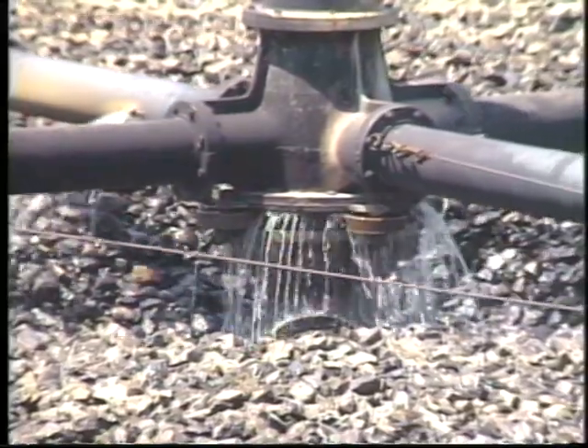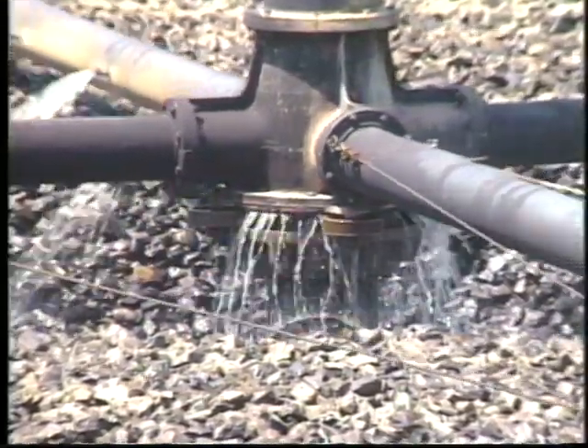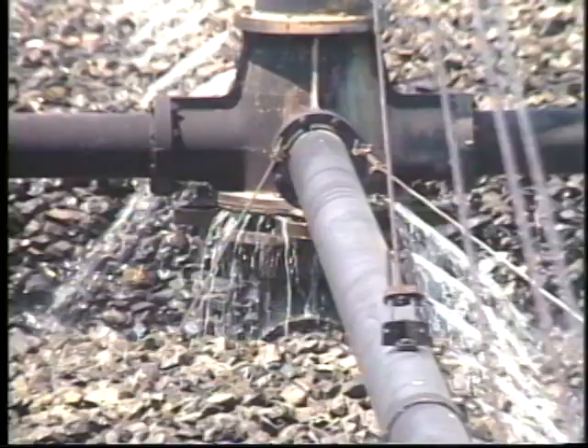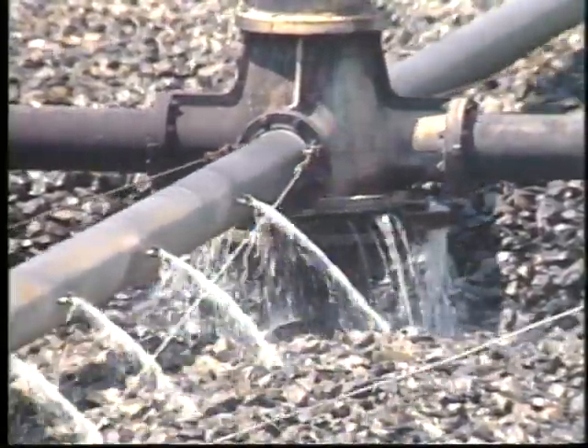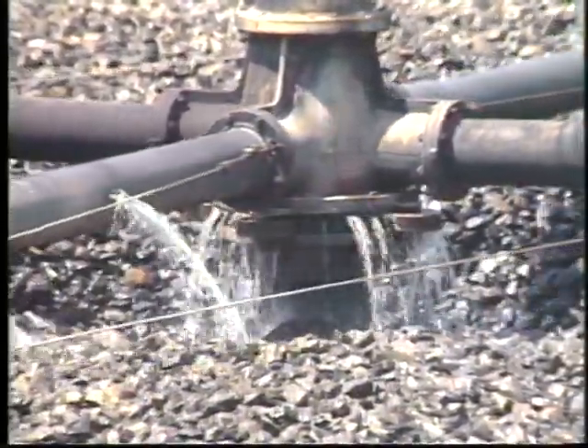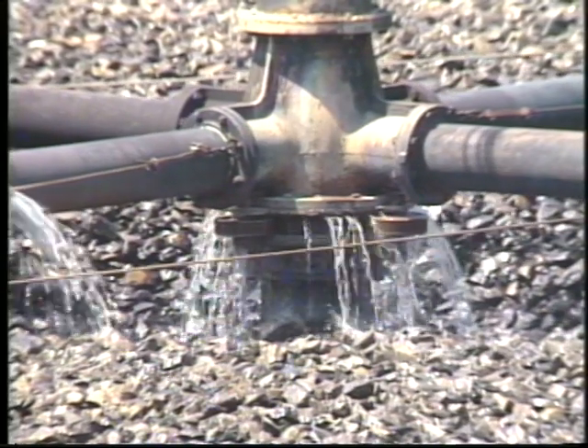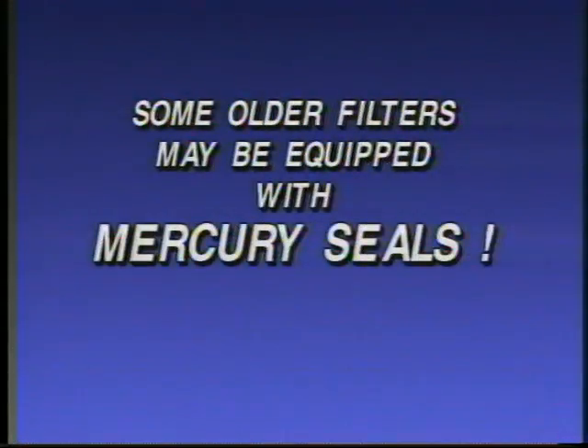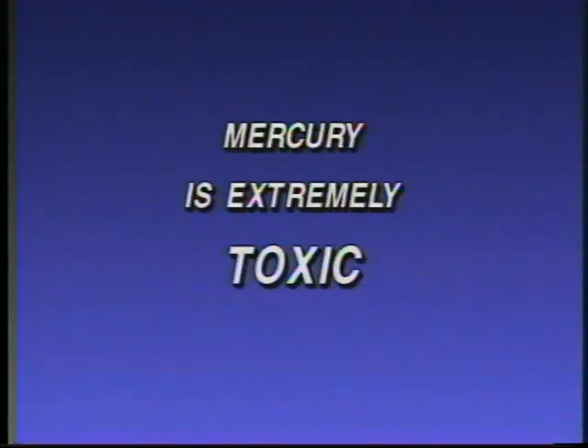If the seal in the center column is leaking excessively, it should be replaced. Leaking seals can lead to poor trickling filter performance. Warning: some older trickling filters may be equipped with mercury seals. Mercury is an extremely toxic element that requires special handling. If your trickling filter is equipped with a mercury seal, notify your local DEP office at once.